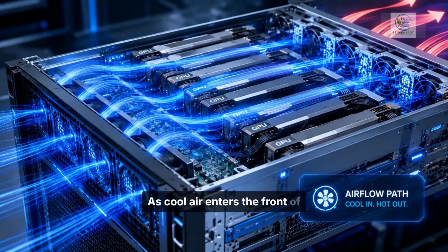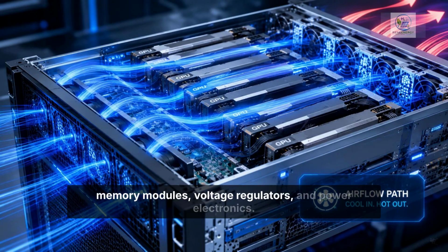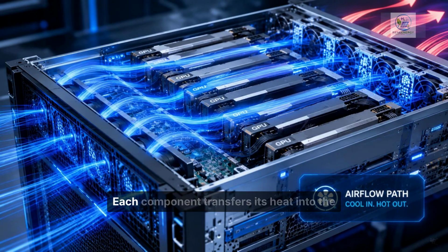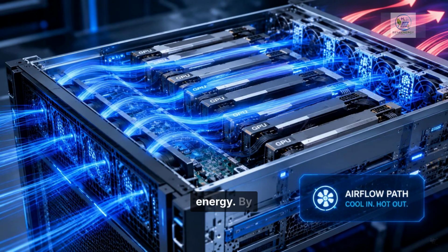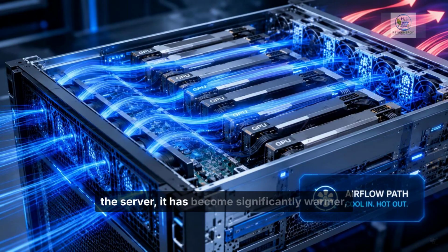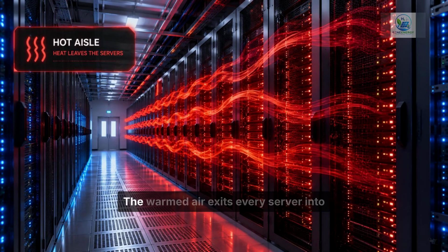As cool air enters the front of each server, high-speed fans immediately pull it across the internal components. The airflow is carefully directed over the GPUs, CPUs, memory modules, voltage regulators, and power electronics. Each component transfers its heat into the moving air through metal heat sinks with hundreds of thin fins that dramatically increase the cooling surface area. Within just fractions of a second, the once cool air absorbs enormous amounts of thermal energy. By the time it reaches the back of the server, it has become significantly warmer, carrying away the heat generated by artificial intelligence. The warmed air exits every server into the hot aisle.